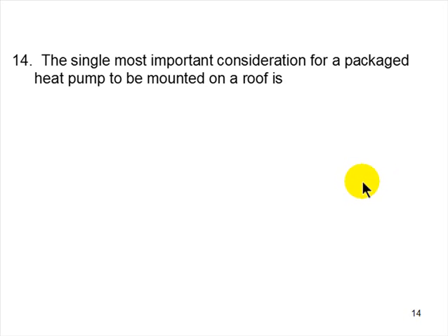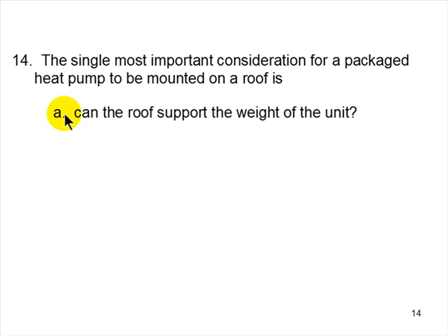14. The single most important consideration for a packaged heat pump to be mounted on a roof is, what's the single most important thing that should occur to you first when you look at a roof and you say, oh, I got to put a packaged heat pump up here? Can the roof support the weight of the unit?